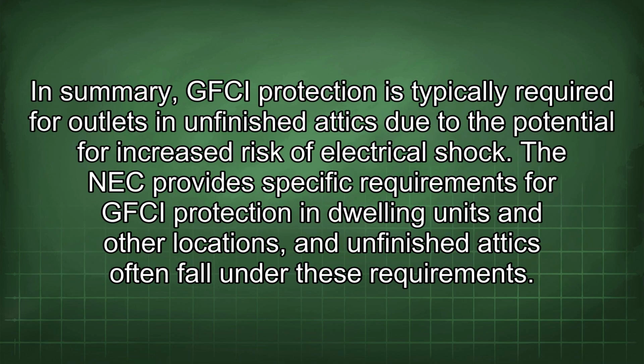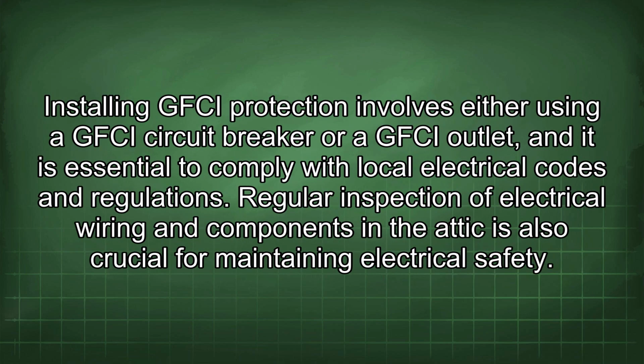In summary, GFCI protection is typically required for outlets in unfinished attics due to the potential for increased risk of electrical shock. The NEC provides specific requirements for GFCI protection in dwelling units and other locations, and unfinished attics often fall under these requirements. Installing GFCI protection involves either using a GFCI circuit breaker or a GFCI outlet, and it is essential to comply with local electrical codes and regulations.